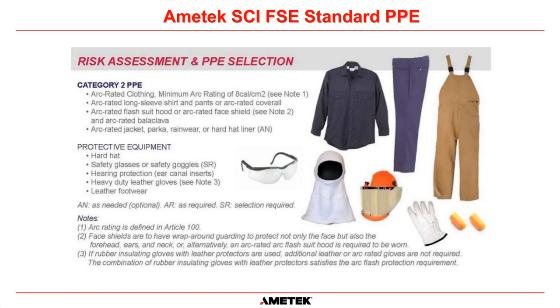And just to let you know, all of our field service guys conform to the NFPA 70E standards, so they wear Category 2 PPE when they are working on the UPS system. So they will have arc flash FRs rated to the correct cal, which has to be 8 cal per centimeter squared or more, arc flash shields, balaclava, safety glasses, earplugs. They will have all of this PPE available to do the maintenance when they're taking live readings. Okay.